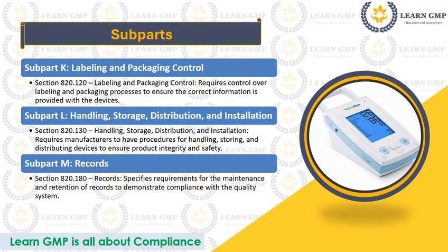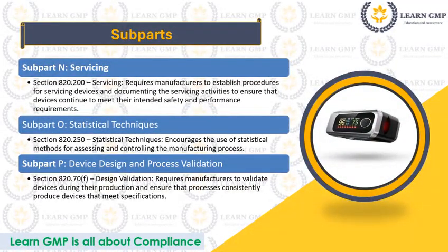Section 820.180, Records, specifies requirements for the maintenance and retention of records to demonstrate compliance with the quality system. Subpart N, Servicing.